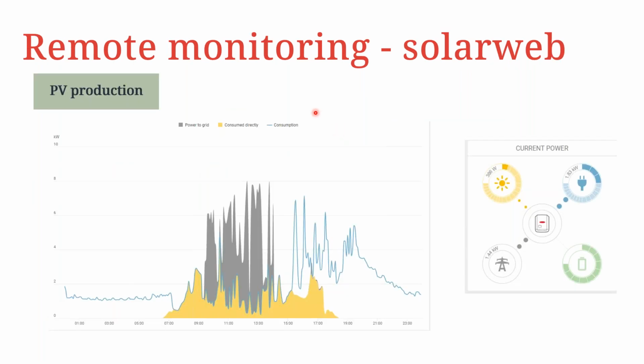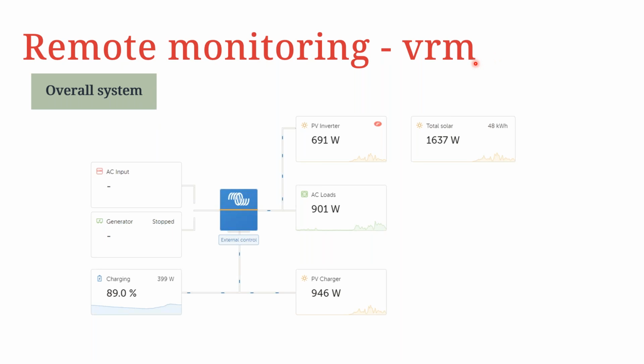When it comes to monitoring, you can do monitoring from Fronius Solar.web, and this would allow you to see PV production data only. But if you would also like to see consumption, you would have to install a Fronius Smart Meter. But for an AC coupled installation where the Fronius is connected to the AC out of the Victron inverter, a Fronius Smart Meter is not required. In this case, if you want to see the overall system, you can do this through the VRM, the Victron monitoring platform. Here you are able to see the status of all the components used for the installation. You can see the PV inverter, the consumption as far as the AC loads are concerned, the MPPT charger if you have one, and also the state of charge of the batteries.